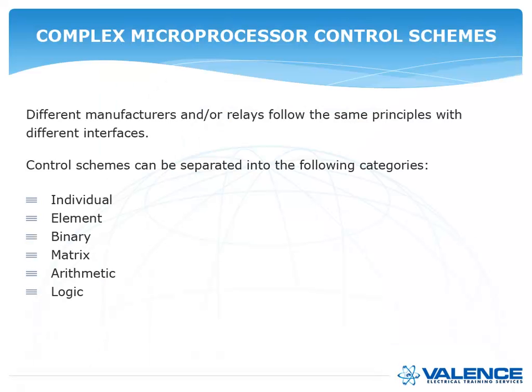When you're talking about digital control schemes, it doesn't matter what manufacturer you're talking about, they all basically break down into the following categories. You can have an individual element scheme, which means you program each element individually. You can have a binary scheme, which is just ones and zeros. You can have a matrix scheme, which is ones and zeros on a chart. Or you can have arithmetic, which is how Schweitzer does it, so everything is broken down into arithmetic symbols. And then you can have a logic system, which is kind of like what I showed you previously.